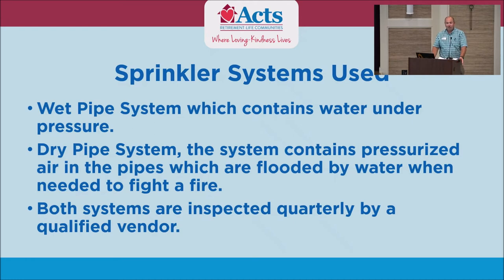If one goes off in an apartment, as has happened before, you run and after confirming there's no fire I'm going to valve it off — but I have to go turn valves off to shut the water to the whole floor down and drain it out to get the pressure off. They do make tools you can put in there to plug them. In training we actually had to take two blocks of wood, stand up and reach above us, and drive a wedge in to stop the water. You do go home wet.